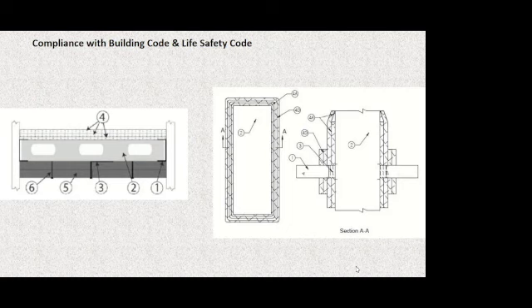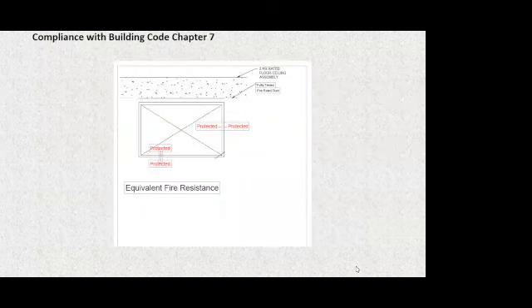What you're looking at is multiple layers of a fire rated product around a duct that could only be best described as SMACNA on steroids, and you just got to the equivalent fire resistance of the drywall assemblies. And if this is not what you're seeing out in the field, you're not getting 2-hour fire resistance. This is what the fire rated duct system must do to be equivalent to those drywall assemblies. When we take the build construction away, if we're not going to have shaft construction, then we need to have the equivalent fire resistance. And that means it needs to be protected from all the same fire scenarios, the same continuity support. Then we have equivalent fire rated duct product on our job.